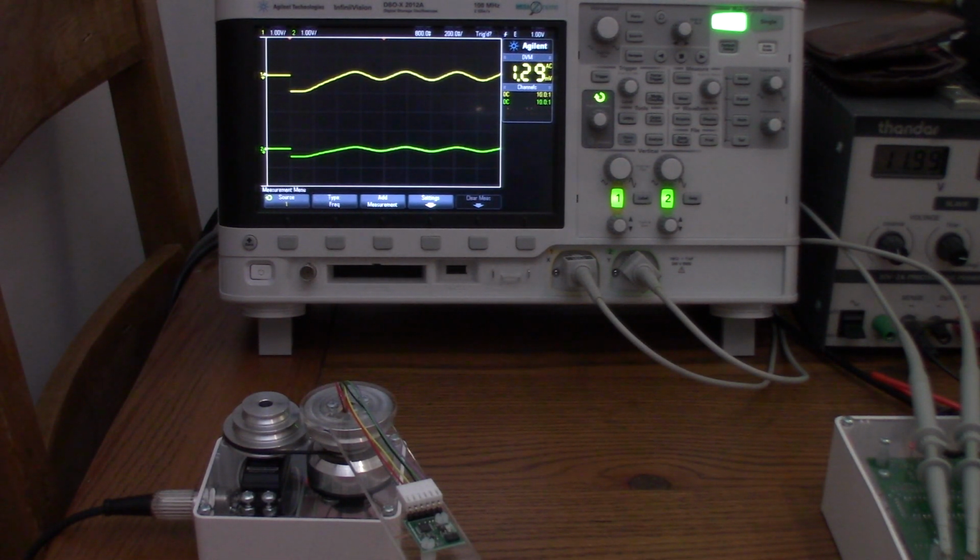But also Ziegler-Nichols states that, let me just, I know that I've got the document here, I'm just going to see if I can pull it up. I think I've got it. I just need to double check the facts. Yes, okay. So in a proportional control system, Ziegler-Nichols suggests that you take the oscillation value and multiply it by a half, and that is the best initial value you should use if it's a purely proportional control. So let's just see if that actually does apply.